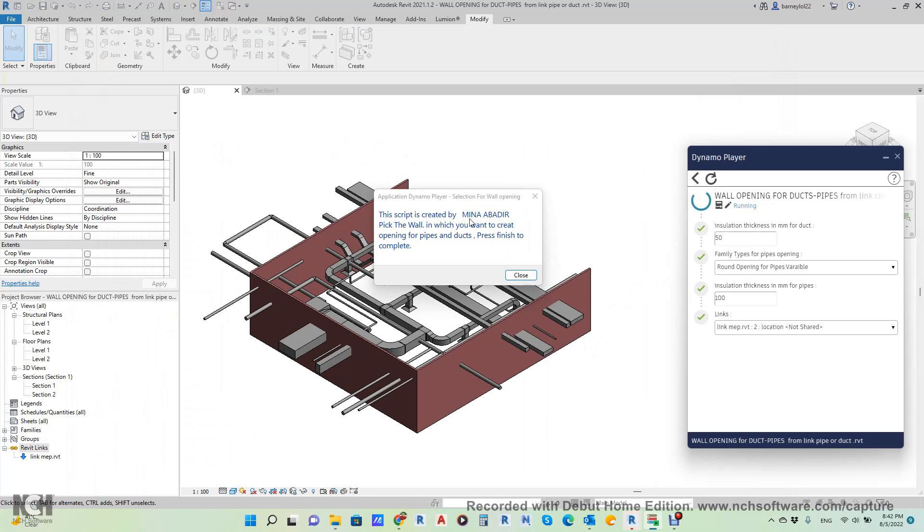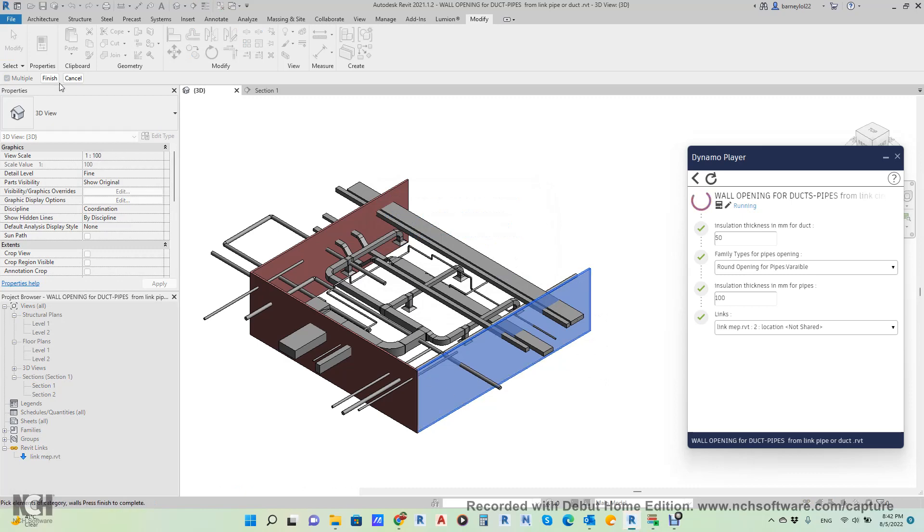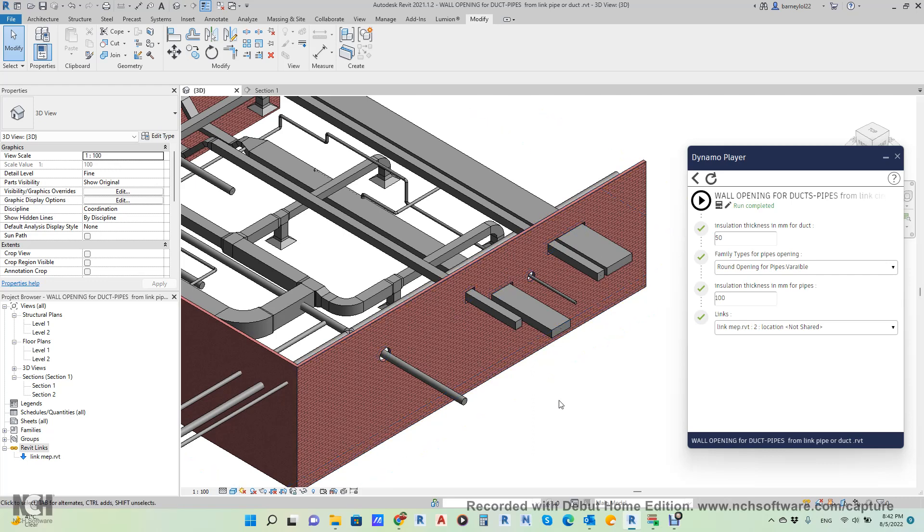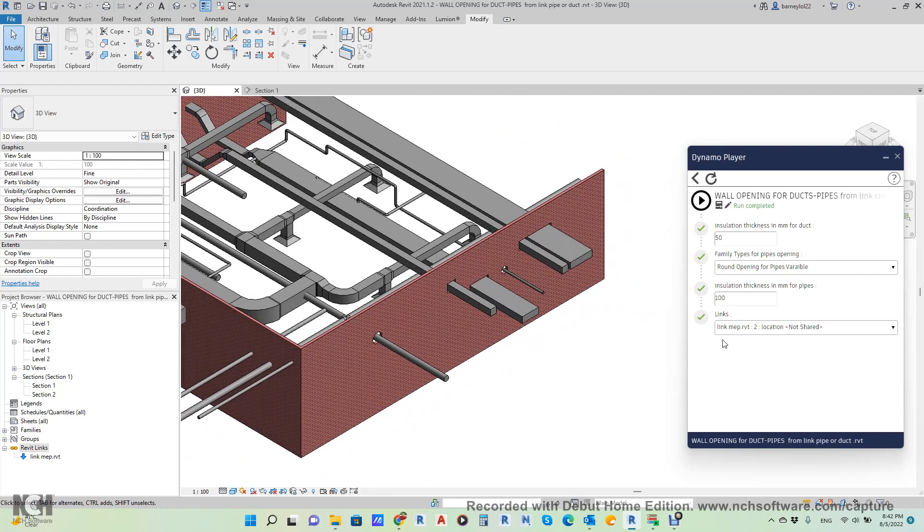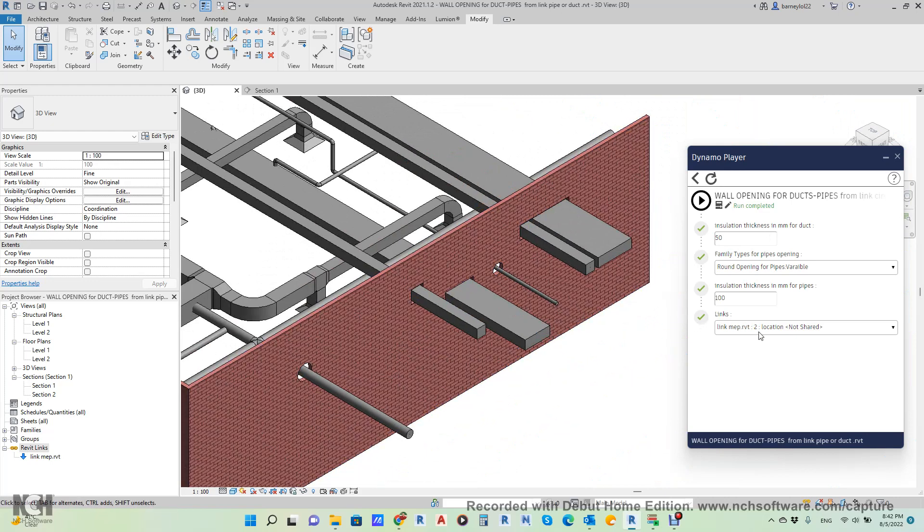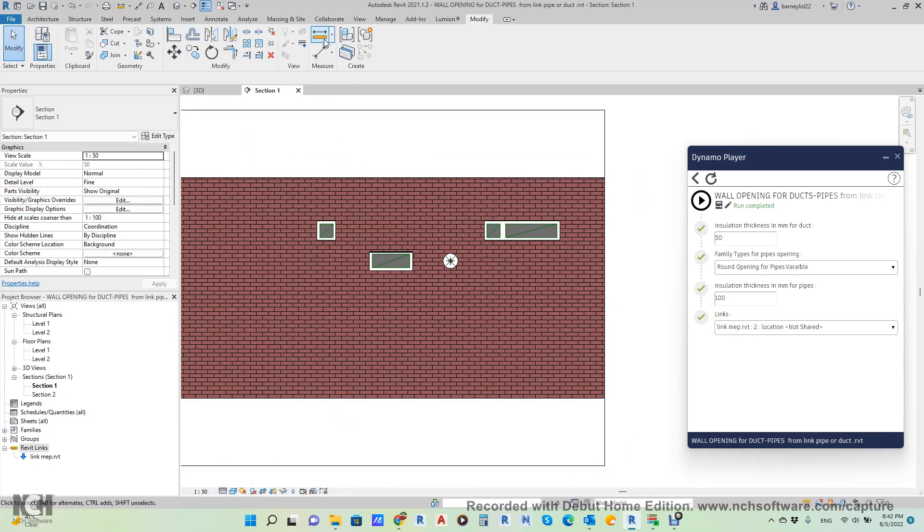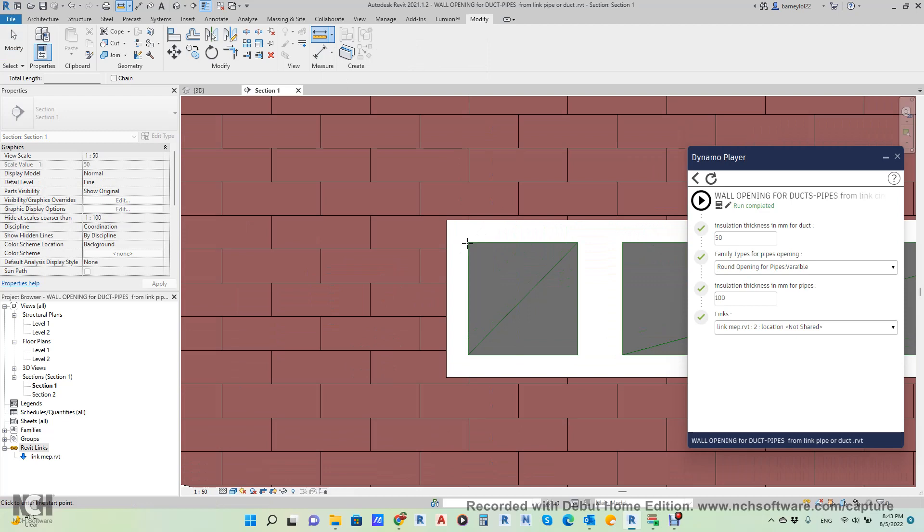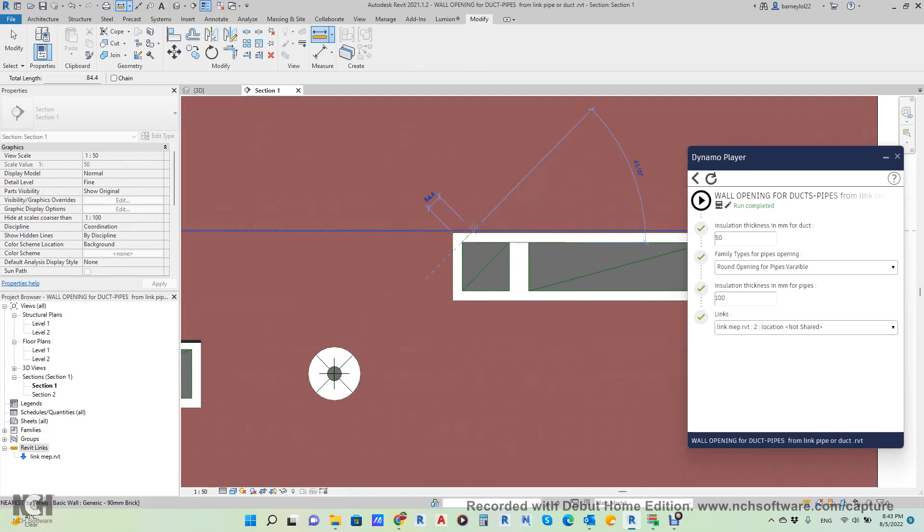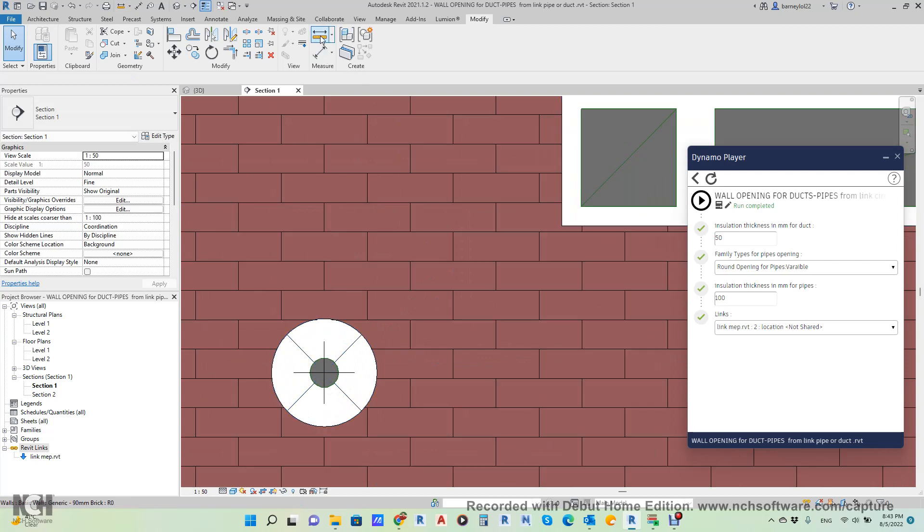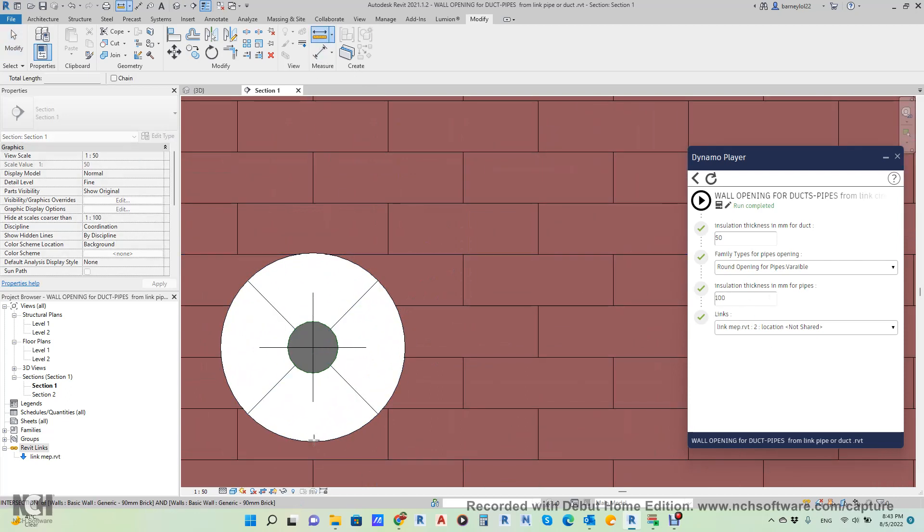It will tell you that this script is done by Mina Abadir. Pick the wall and click finish. So this is the wall you want to make the penetration, then click finish. Simply he will make all the openings for you with the dimensions you asked for. You asked for thickness for the duct to be 50, then this distance will be 50. You asked for the pipe to be 100, then he will make it 100. Let me make a section here. So this is 50 and here 50, and here you will find it 100 because we asked for 100.